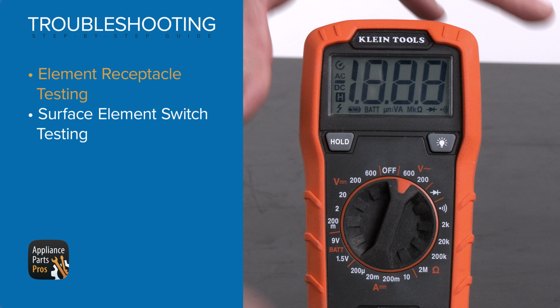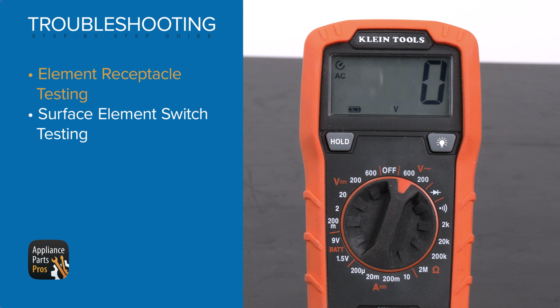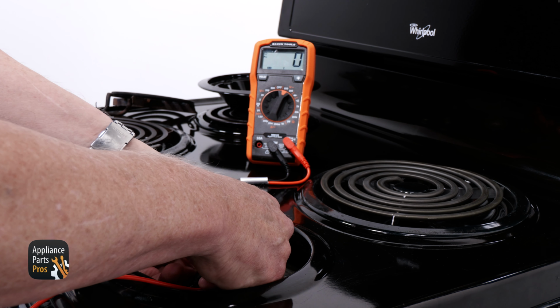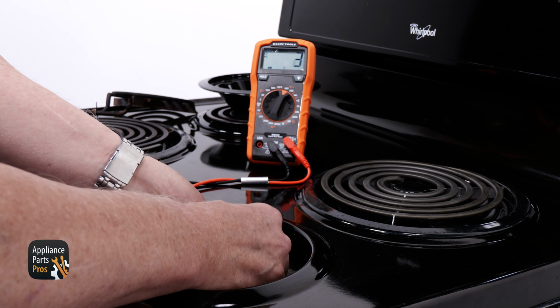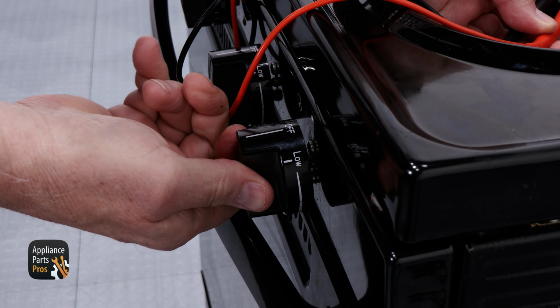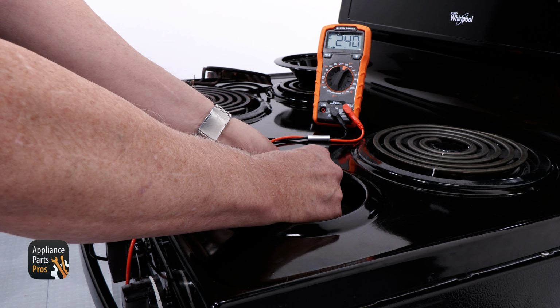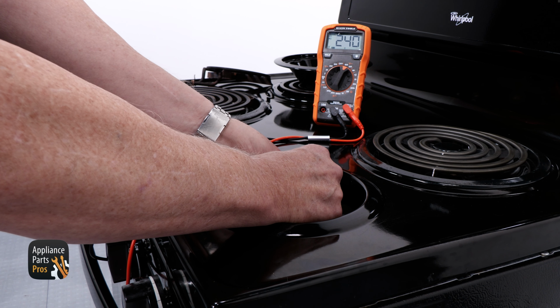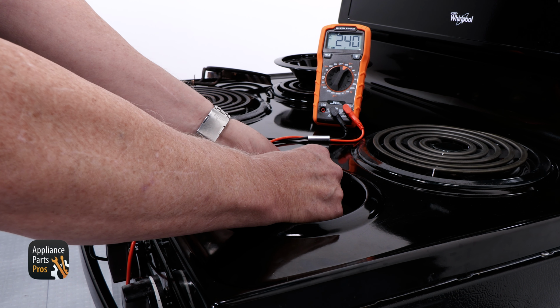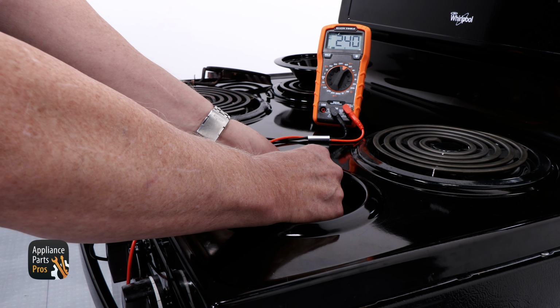Then we can set a multimeter to AC voltage. You're going to put one probe in one slot of the terminal block and the other probe in the other slot, then turn the switch on. If your multimeter reads 240 volts AC, then your switch is sending the right amount of voltage to the element.